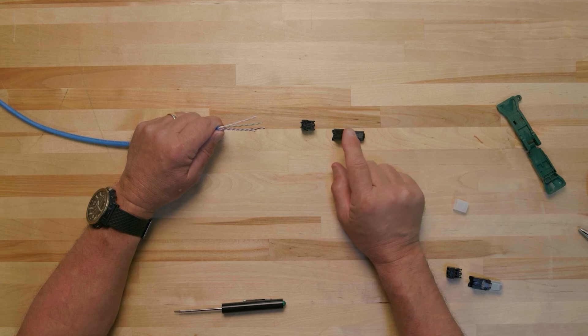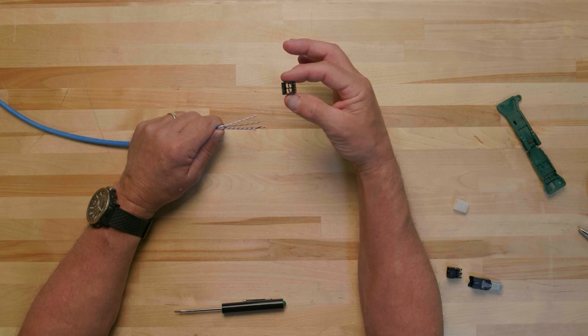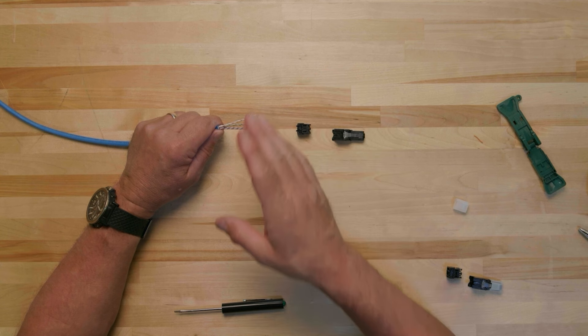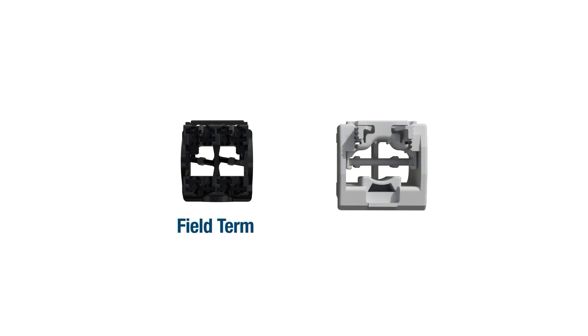Now that the cable is prepared and we understand the proper way to orient the cable, we can perform the termination. The steps to terminating the RJ45 field term plug are almost identical to the shielded TG jack, except for two main differences. The first difference is that the field term plug is male, while the TG jack module is female. The retaining latch on the field term plug snaps into the TG jack module to couple them together. The second difference is the size of the wire caps — each quadrant of the field term wire cap is shorter than the TG wire cap, meaning these two wire caps are not interchangeable.